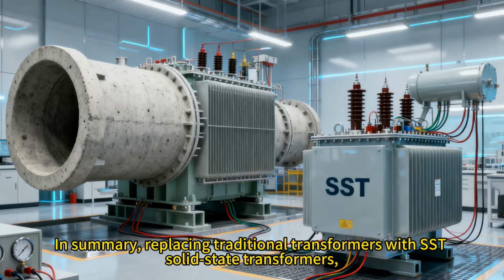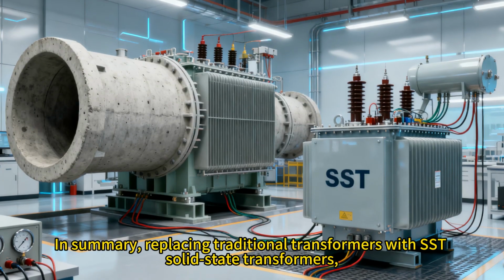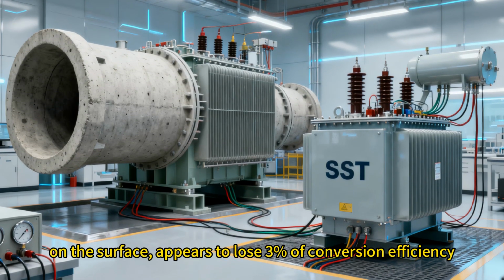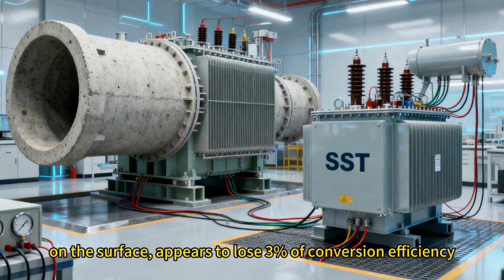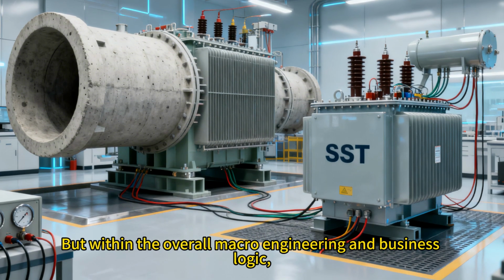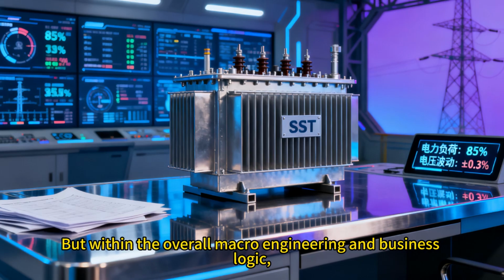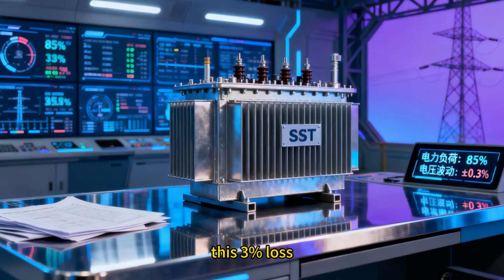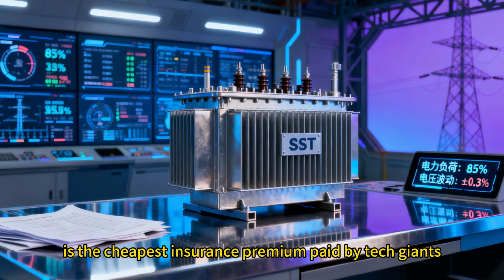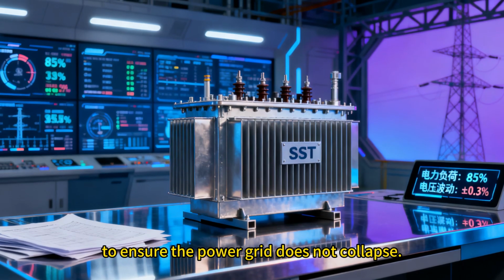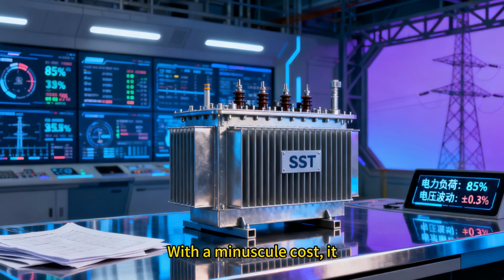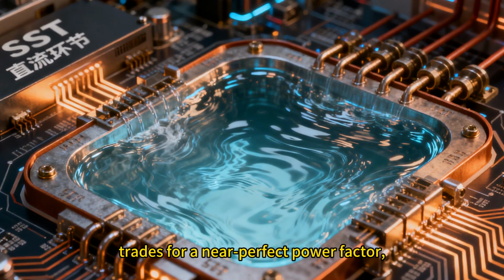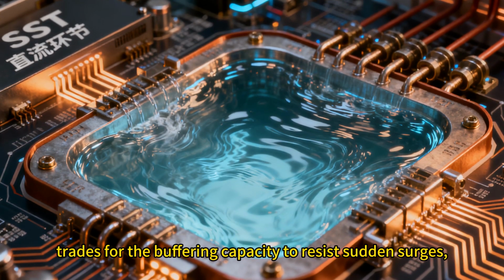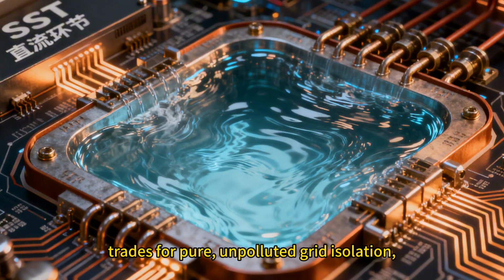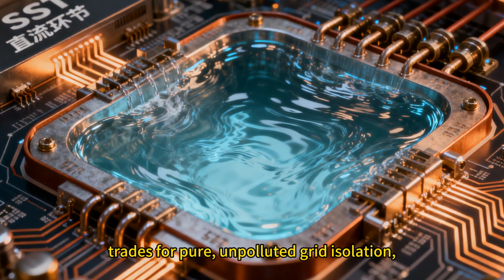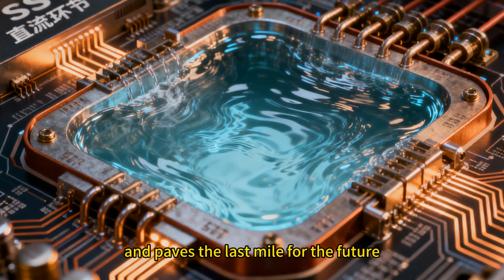In summary, replacing traditional transformers with SST solid-state transformers on the surface appears to lose 3% of conversion efficiency and create a bit more heat, but within the overall macro engineering and business logic, this 3% loss is the cheapest insurance premium paid by tech giants to ensure the power grid does not collapse. With a minuscule cost, it trades for a near-perfect power factor, trades for the buffering capacity to resist sudden surges, trades for pure, unpolluted grid isolation, and paves the last mile for the future.